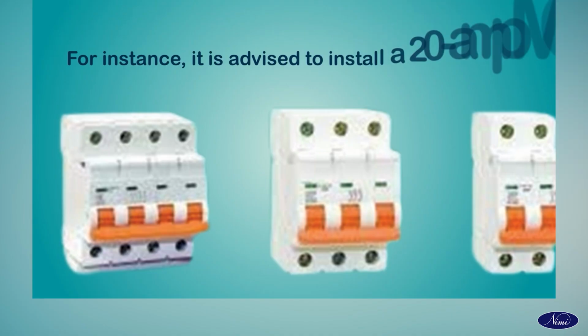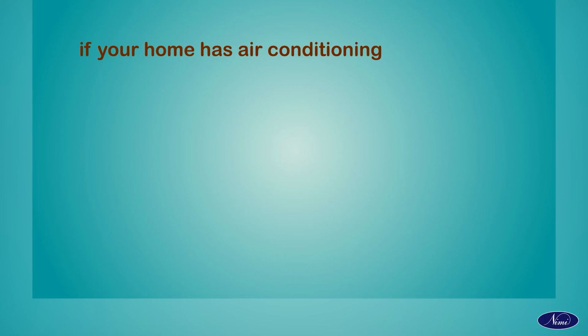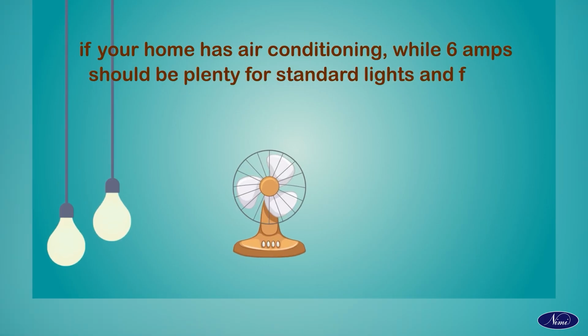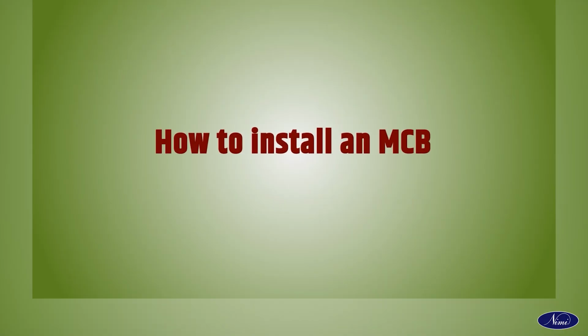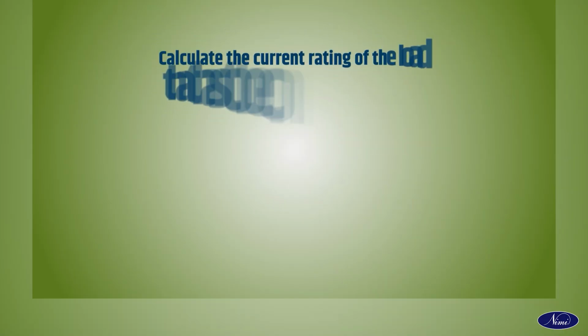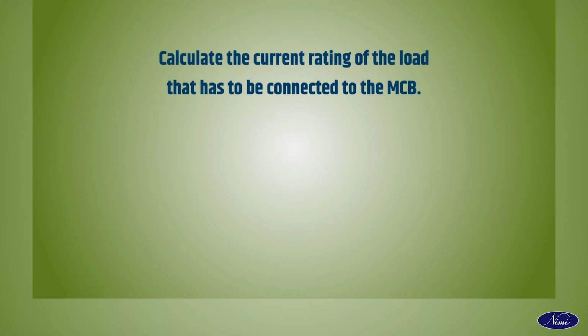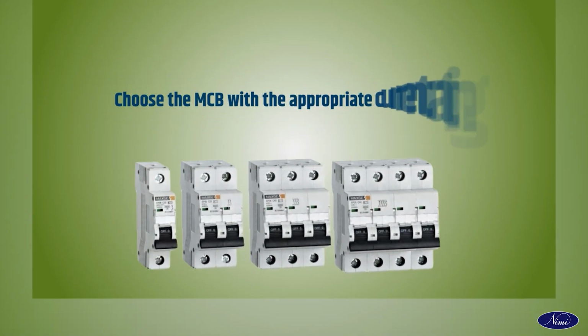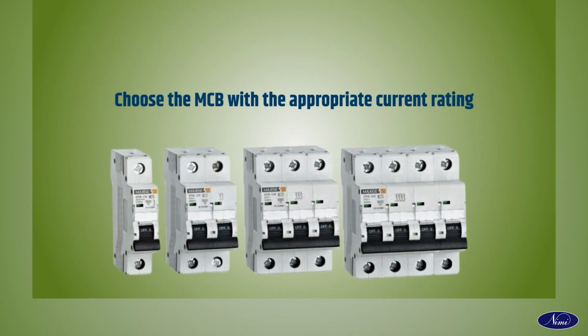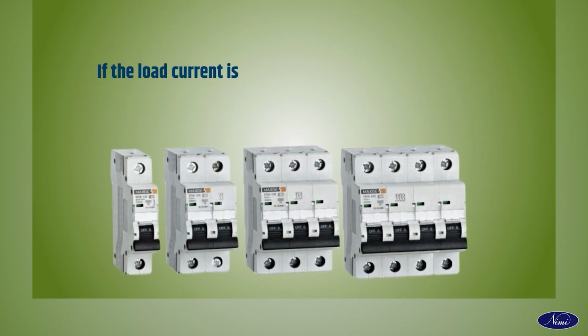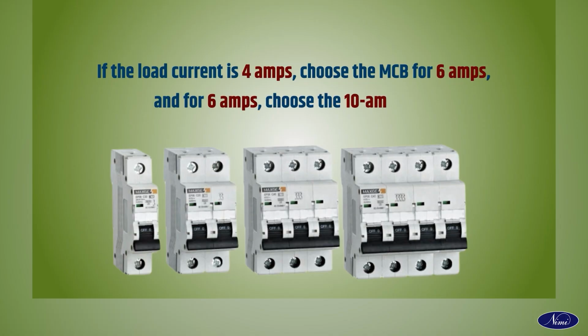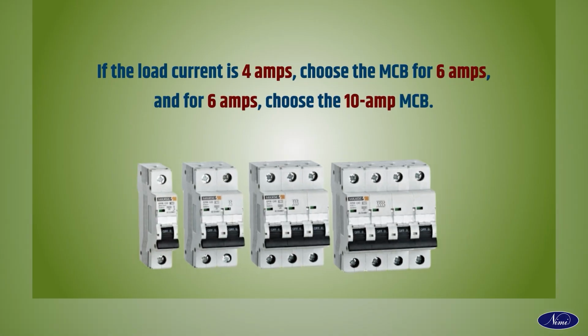For instance, it is advised to install a 20 amp MCB if your home has air conditioning, while 6 amps should be plenty for standard lights and fans. How to install an MCB? Calculate the current rating of the load that has to be connected to the MCB. Choose the MCB with the appropriate current rating for the load. If the load current is 4 amps, choose the MCB for 6 amps. If the load current is 6 amps, choose the 10 amp MCB.